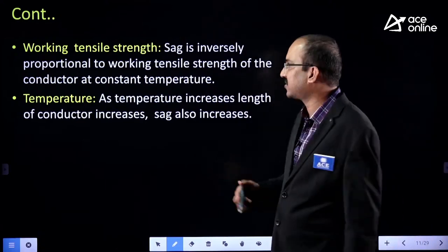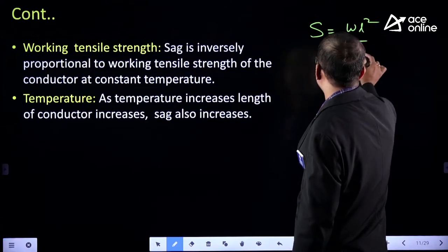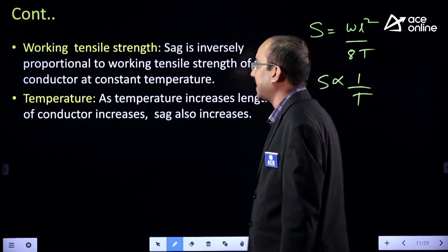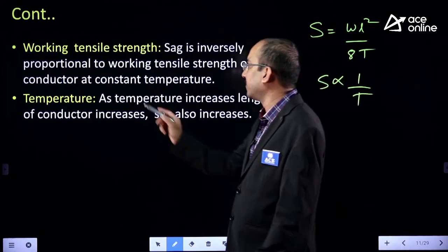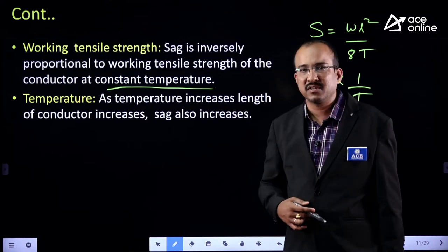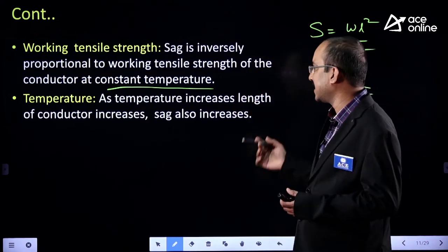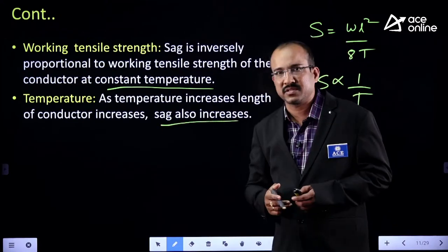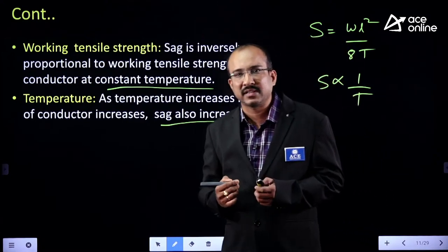What about temperature? SAG also depends on temperature. As temperature increases, the length of the conductor increases, so SAG also increases. These are the factors influencing SAG: weight of the conductor, length of the span, working tensile strength, and temperature.